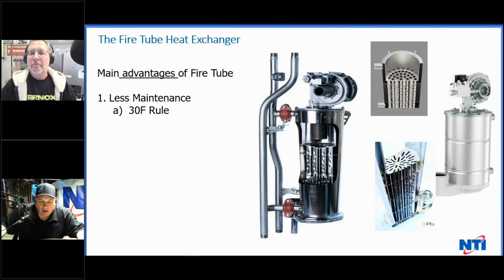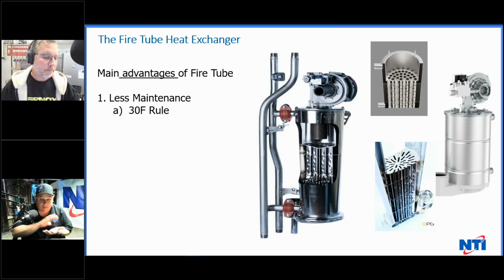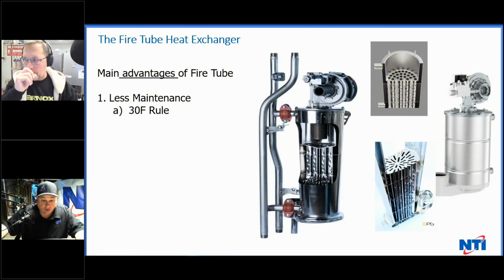Steve, the other thing is, if you get the right kit, they can get everything they need to replace on that boiler, and they can bring a service kit. When you go out, you take an igniter, a sensor, and a fiber board that is guaranteed to break. You are correct about it. It is guaranteed to break after a couple years, and if they don't have it, they're screwed. That service kit can save their butt. It can really save them from a headache.